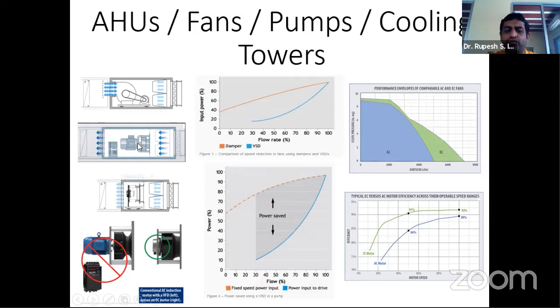Then we came on to the motor driven or the plug fans, what we called it, with the VSD system itself, which was the next generation. But now we have something called the EC motor. So that could be instead of my motor and my VFD, I have a small plug which is attached to the fan, which does the dual role.